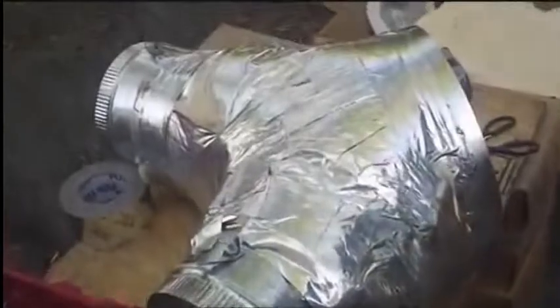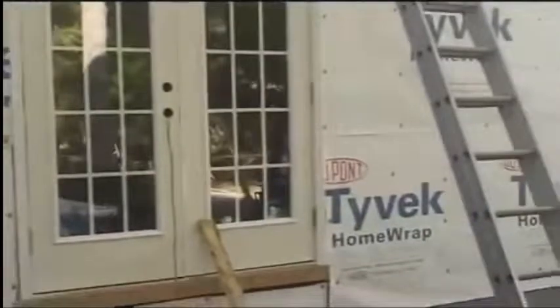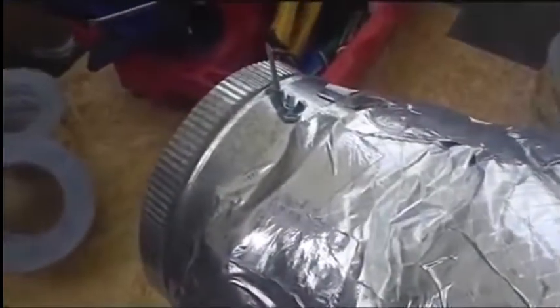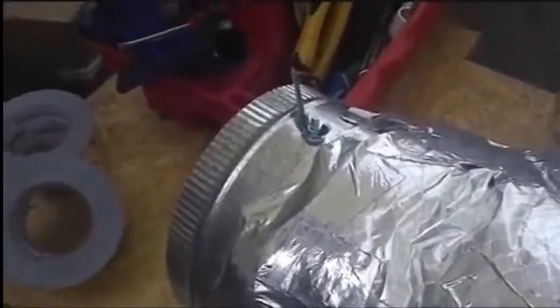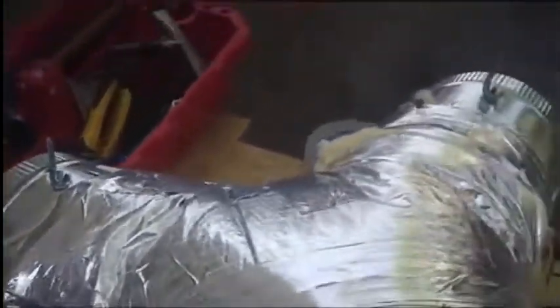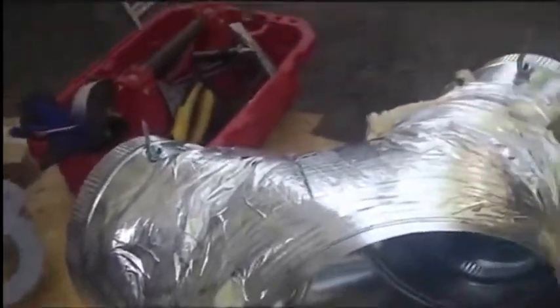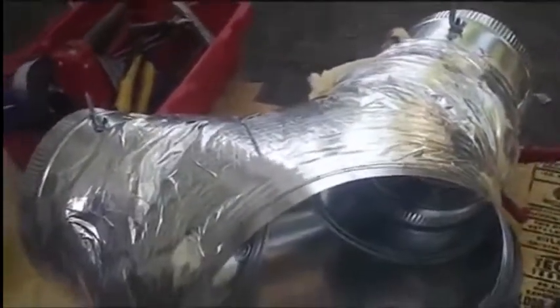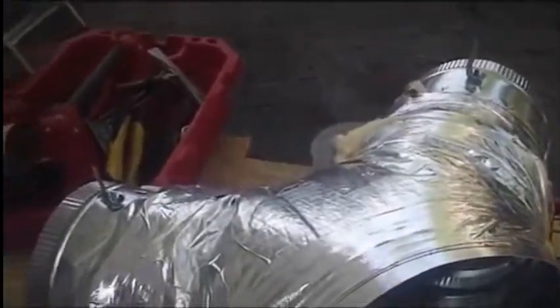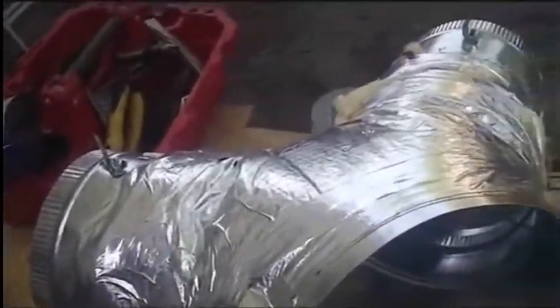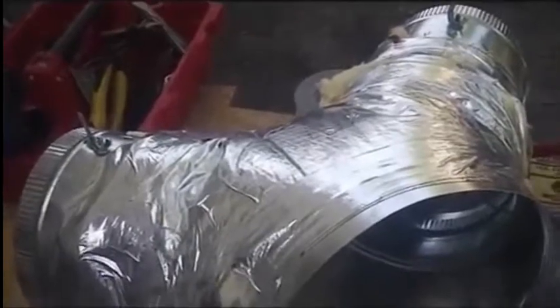Alright, we have a Y fitting here, starting at 14 inches and going to 10-inch and 9-inch. The 9-inch section will serve the lower addition here, and the 10-inch section will serve the rest of the house, the southern section. I have dampers on both because we're adding onto an existing system we're going to change out later this summer, so I want to control the airflow since it's not a perfect setup until we redo the trunk.